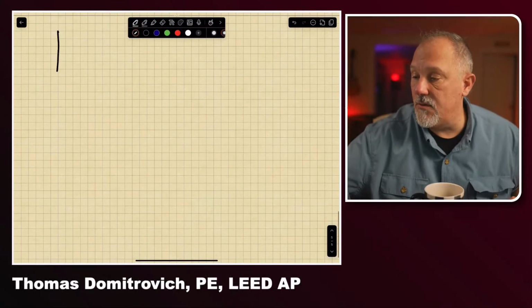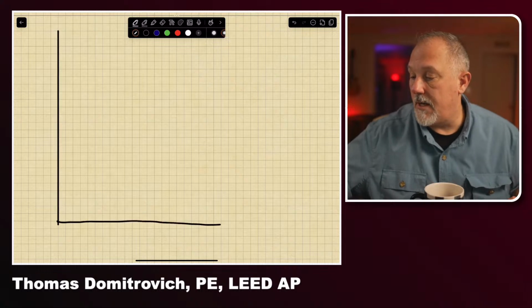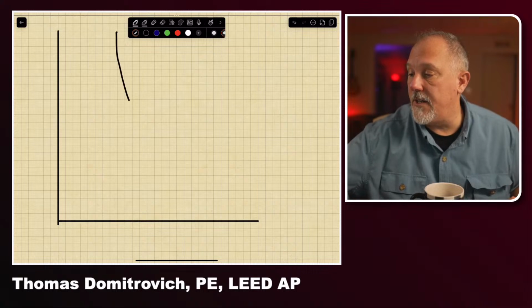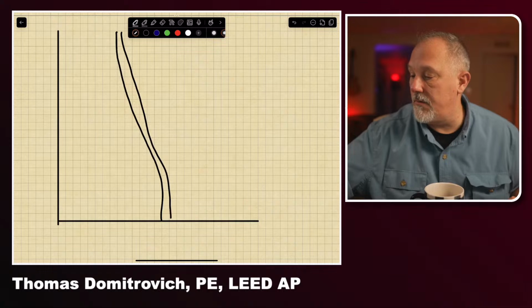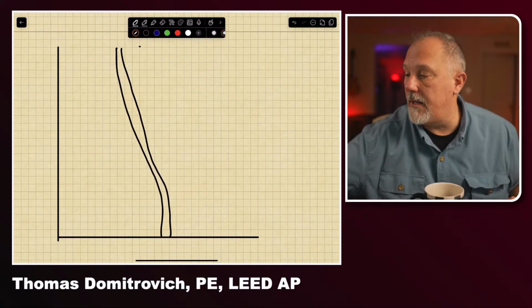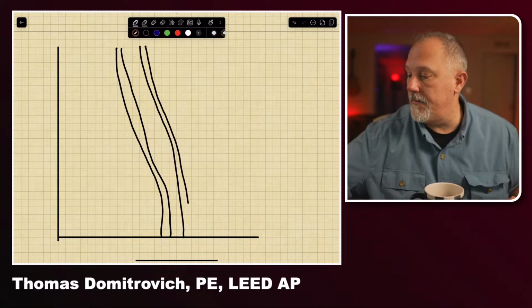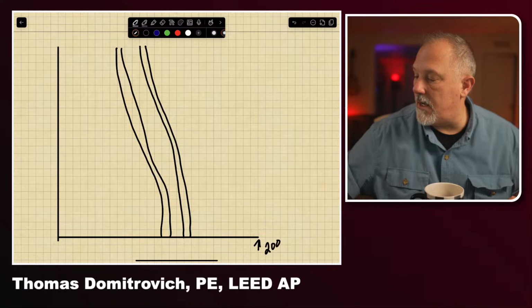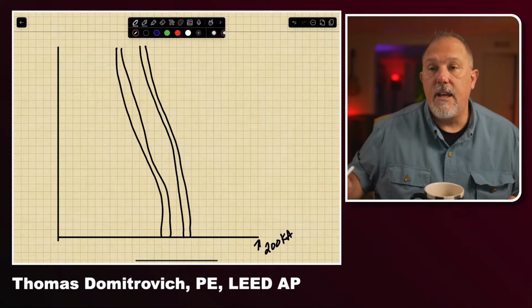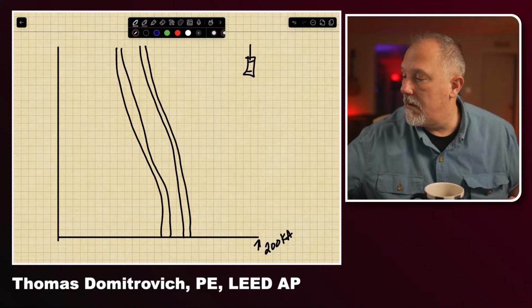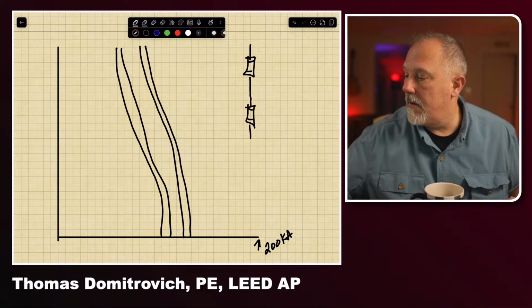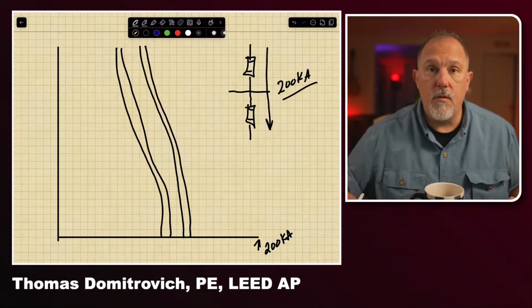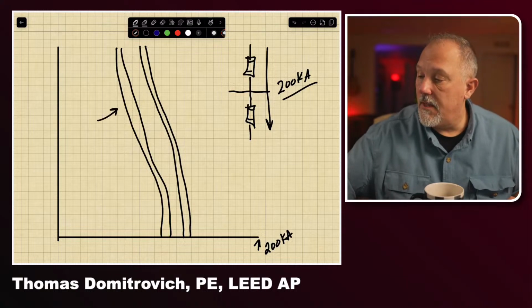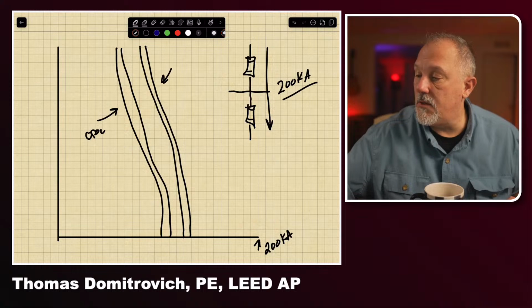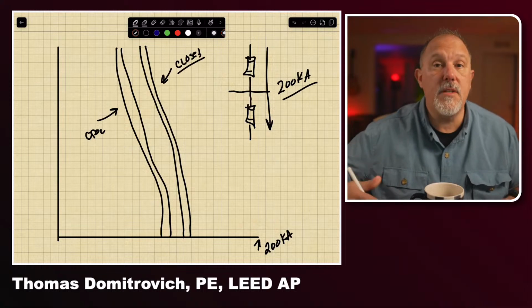That means that if I drew my TCC curves, I'm getting to you, David Engelhardt. Don't worry, buddy. If I drew my TCC curves, and I'm going to draw 2 fuse curves, say that's one, and let's say that this is another. And let's say that this is 200,000 amps. If I had 200,000 amps flowing through both of these, that fuse would open and this fuse would stay closed up to the interrupting rating.